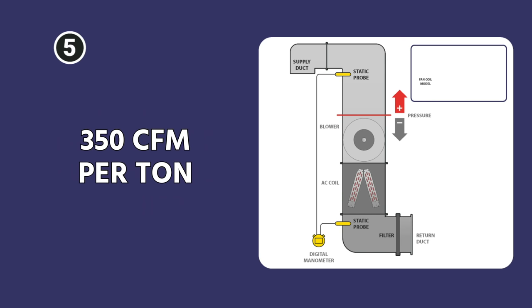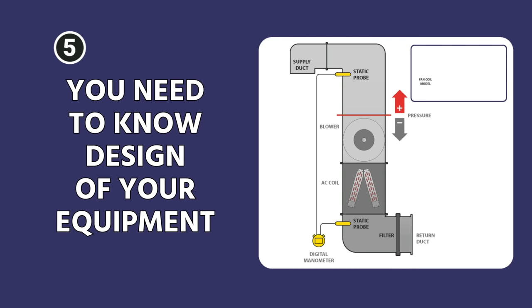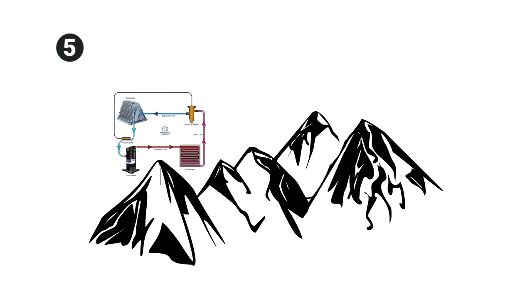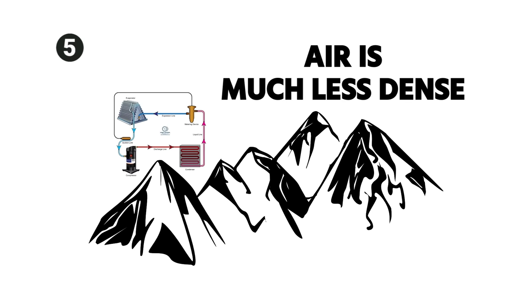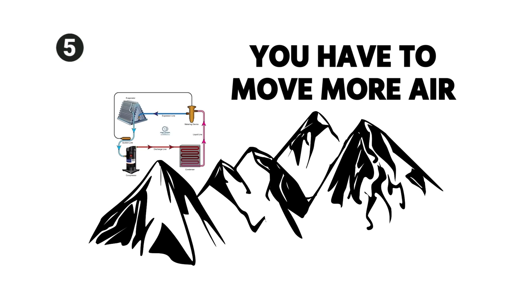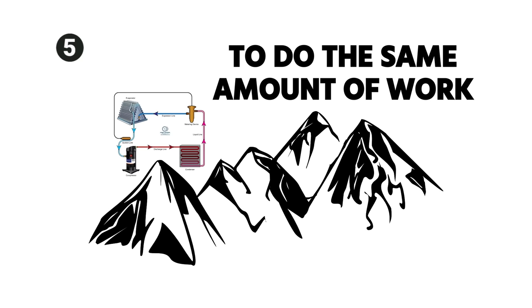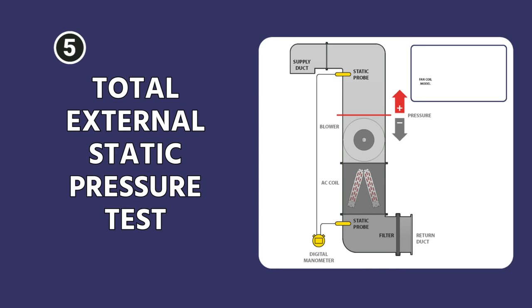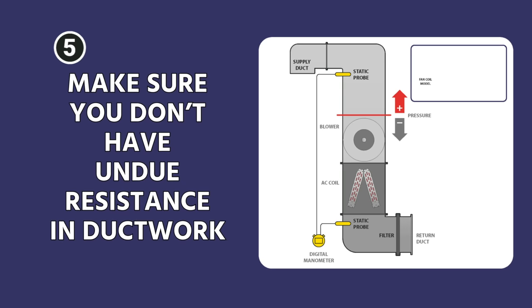People will throw around 350 CFM per ton, or 400 CFM per ton, or 500 CFM per ton, but you need to know the design of your particular piece of equipment to know what target you are trying to hit. For example, if you have a system up in the mountains where the air is much less dense, you have to move more air to do the same amount of work because the air weighs less. Once you've established that, you can do a total external static pressure test on the system to make sure that you don't have undue resistance in your ductwork.